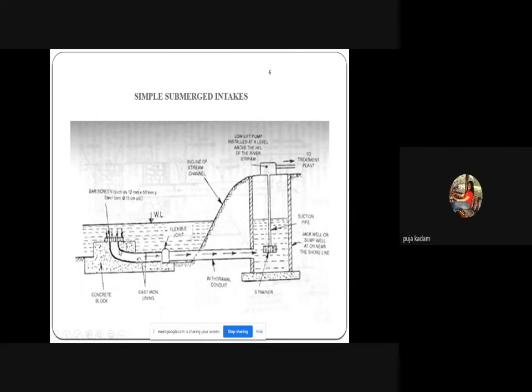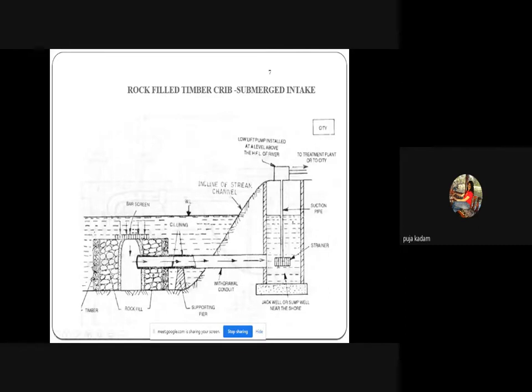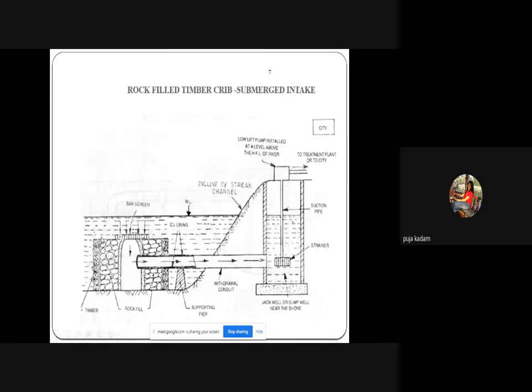In the simple submerged intake structure, water is collected through a pipeline which has a strainer or screening to avoid entry of debris or floating matter, then passes through the jack well or sump well. A suction pipe with a strainer and pump draws water from the well and passes it to the treatment plant. The key feature is that the entire water collection structure is submerged inside the water source.